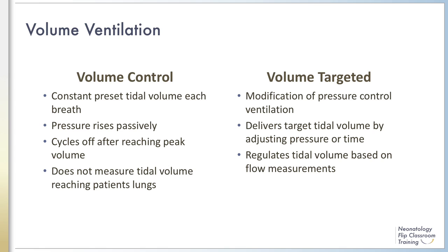In addition, there were a variety of modalities used in the study as comparators, limiting generalization. Though often used interchangeably, there is a difference between volume controlled and volume targeted ventilation. Volume control delivers a constant and preset tidal volume into the ventilator circuit with each breath. The pressure rises passively and generates enough pressure necessary to reach the set tidal volume into the circuit. Inflation cycles off when the peak volume is reached. This mode requires a maximum inflation time and pressure to be set as safety measures.